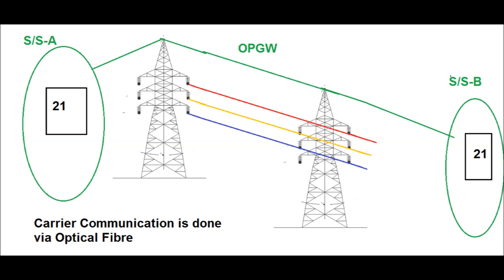As the earth wire, optical fiber ground wire is used. On the outside it provides direct protection from lightning to the phase conductors and also provides the return path for any phase-to-ground fault. The function of the optical fiber is to provide digital communication for carrier communication between substations located at both ends.